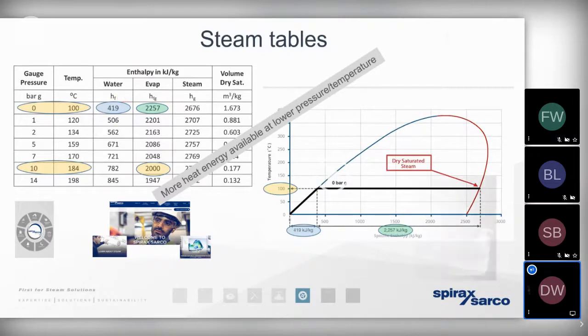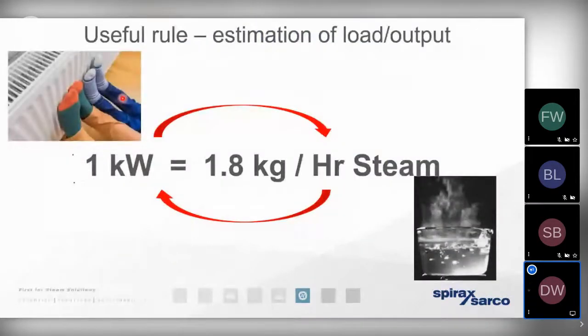So it's also worth bearing in mind that there's quite a useful rule of thumb when it comes to understanding the mass of steam required to heat a process, and also the energy content of a mass of steam. And that very broad and useful rule of thumb tells us that if we've got a process that requires 1 kilowatt, it needs to be supplied with approximately 1.8 kilograms per hour of steam. And conversely, 1.8 kilograms per hour of steam is capable of providing 1 kilowatt of energy to a process.